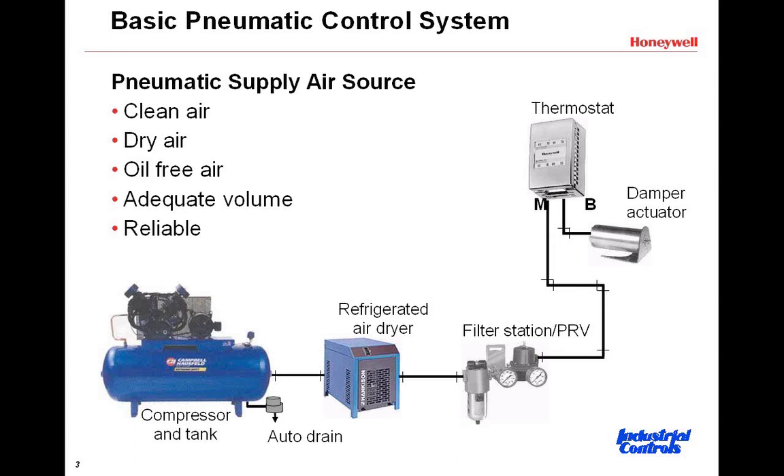It's easy to forget this type of equipment because it's often in a part of the building that doesn't get visited often, but its importance can't be overstated. As a means of testing periodically to prove that equipment is working, you can take any branch air line and use a white piece of cloth or fiber material to allow air to pass and look for spots that might be oily. You might also see contamination if you look at the free end of a piece of polytubing. These are indications that you should spend time in the equipment room looking at the dryer, filters, and compressor.